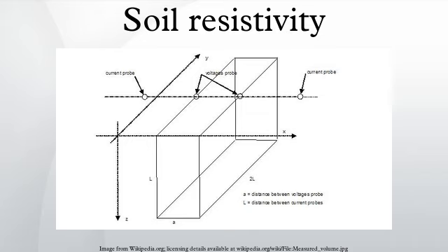The conversion between values measured using the Schlumberger and Wenner methods is possible only in an approximate way. In any case, for both Wenner and Schlumberger methods the electrode spacing between the current probes corresponds to the depth of soil investigation, and the measured apparent soil resistivity is referred to a soil volume as in the figure aside. The current tends to flow near the surface for small probe spacing, whereas more current penetrates deeper soils for large spacing. Thus, it is usually a reasonable approximation to assume that the resistivity measured for a given current probe spacing represents the apparent resistivity of the soil to a depth of L when soil layer resistivity contrasts are not excessive.